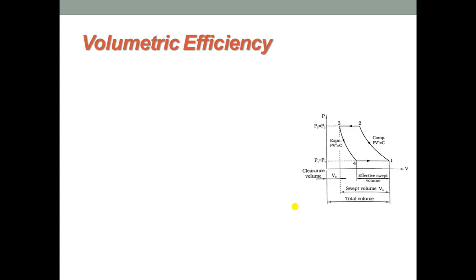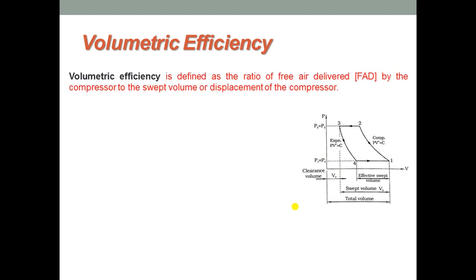Volumetric efficiency is defined as the ratio of free air delivery (FAD) delivered by the compressor to the swept volume or displacement of the compressor. Mathematically, it is FAD over swept volume Vs. FAD is given by V1 minus V4, and the swept volume is given by V1 minus V3, as observed in the PV diagram.